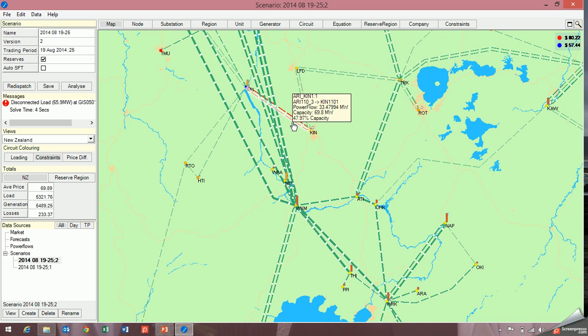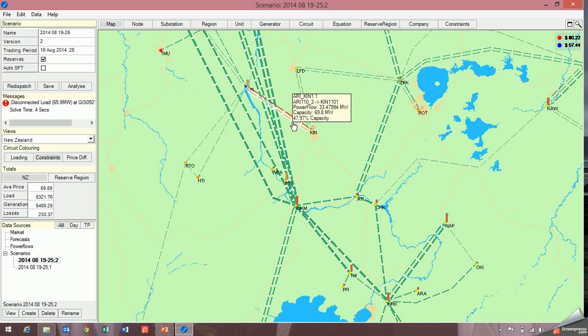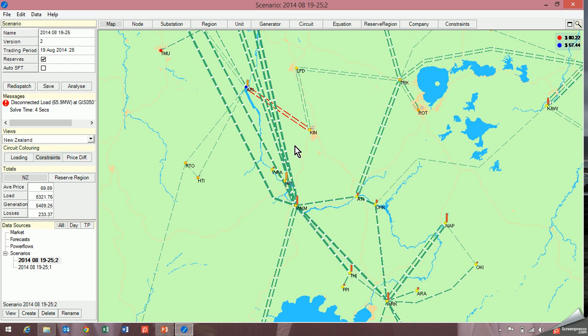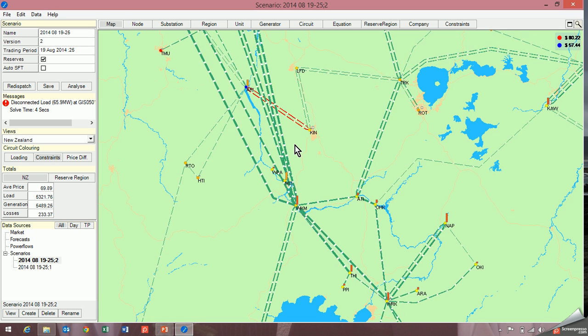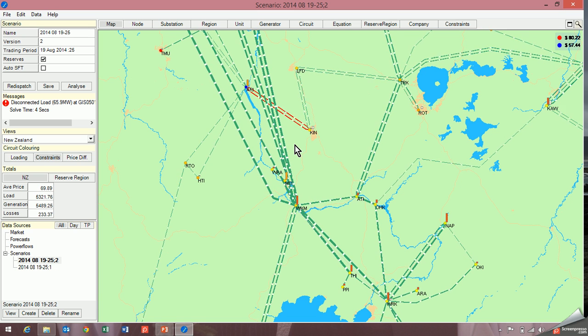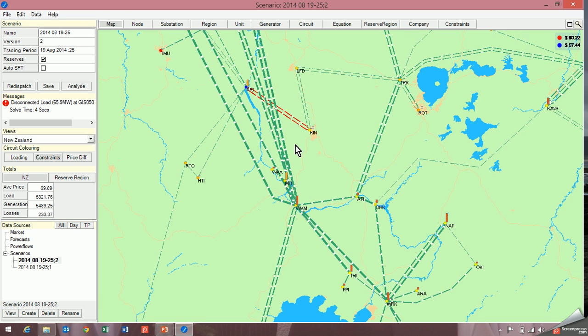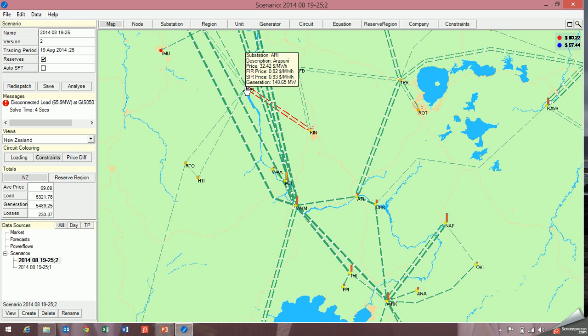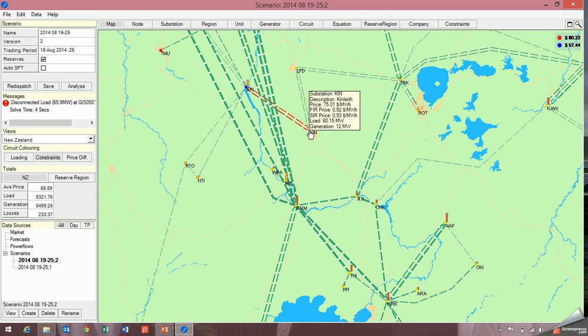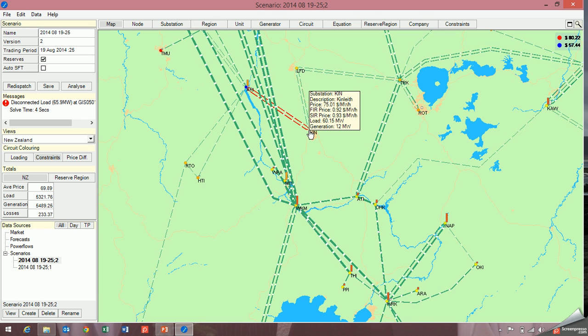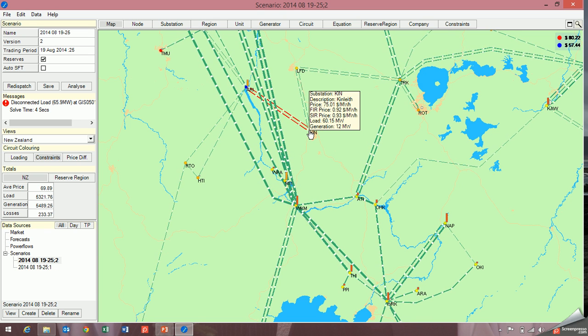They are running red, so they are actually constrained by that equation constraint which we saw before. And I'm expecting to see a price separation between those two nodes which is greater than what one would expect with losses. So the price at the Arapuni substation is 32, and up at Kinleith it is 75. So that's a large price separation which is caused by that constraint.